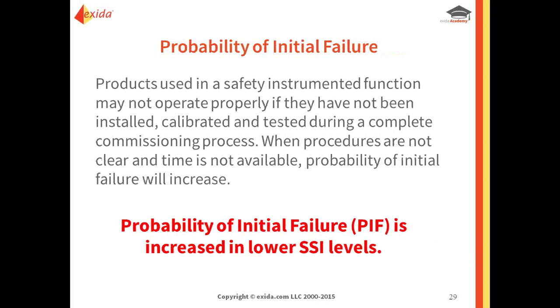What about the probability of initial failure? Well, products are used in a safety instrumented function may not operate properly if they have not been installed correctly, calibrated correctly, or tested during that complete commissioning process.